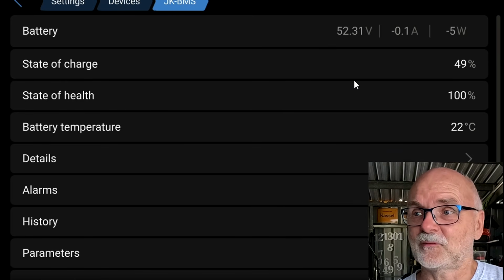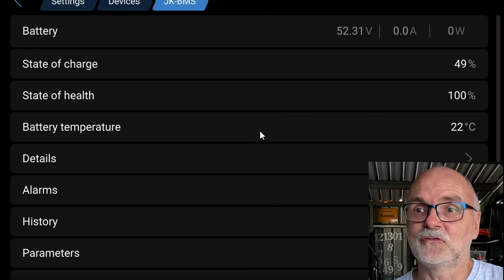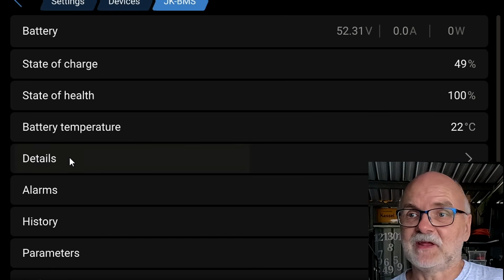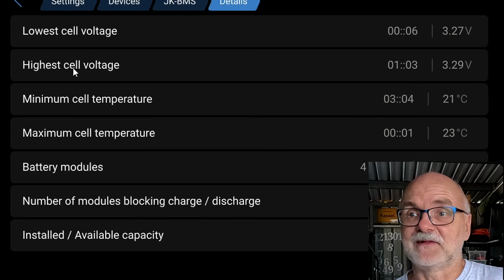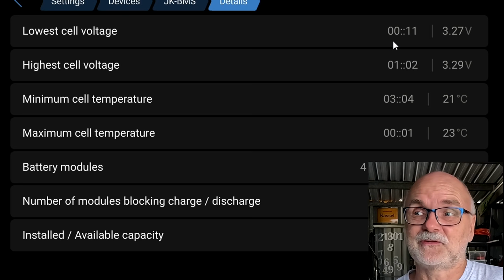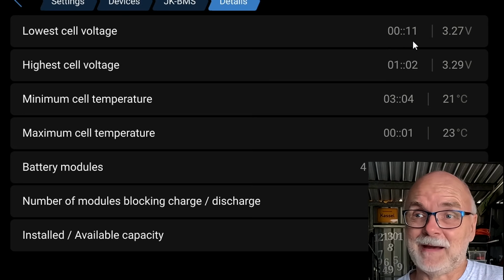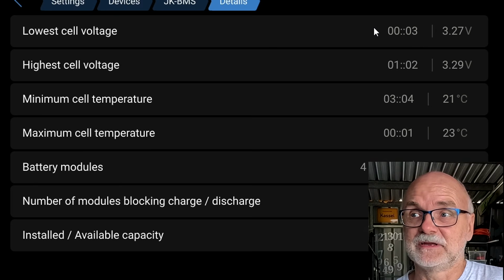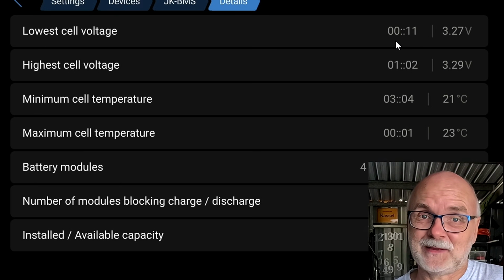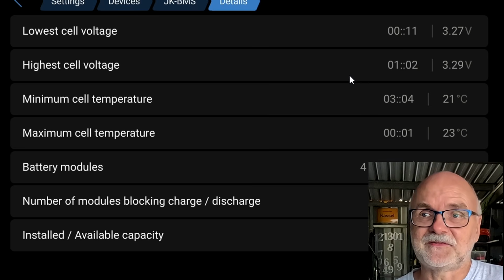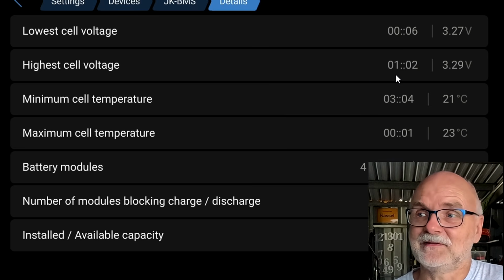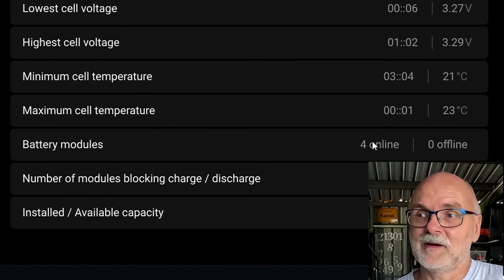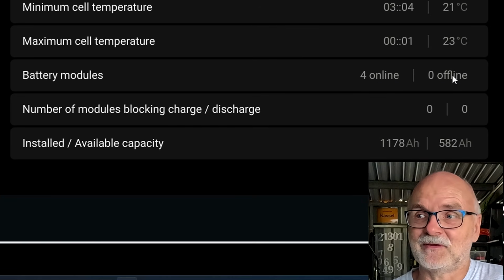What's going on? State of health 100%, battery temperature 22 degrees. So here, if you go into details, we can see the lowest and highest cell voltage as well as the minimum and maximum cell temperature. And here on the right, it also tells you the module and the cell number of your lowest cell voltage. So 00 means this is the master BMS, all dip switches are on 0, and you can see the highest cell voltage is in module number 1, cell number 2, minimum temperature in module number 3, and maximum temperature is in the master again. We've got 4 modules online, everything is okay, nothing is offline.